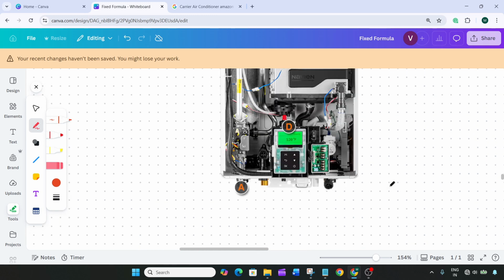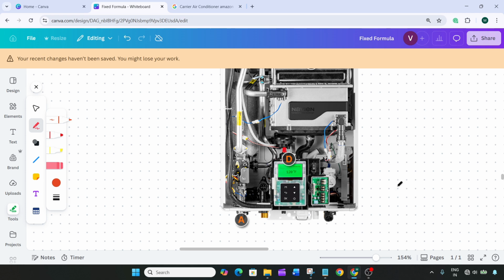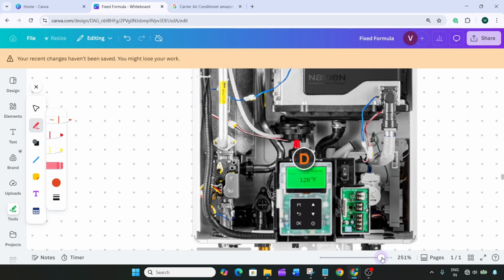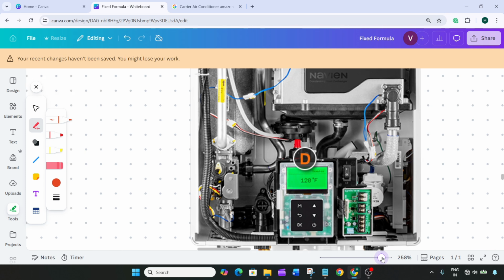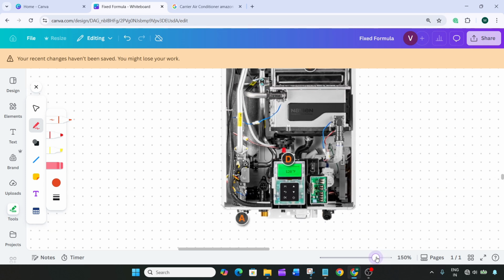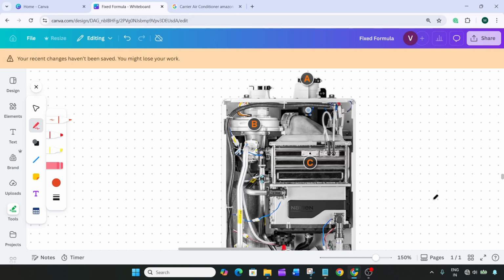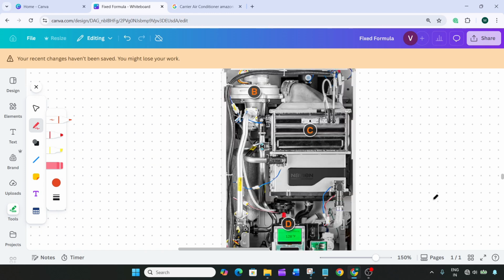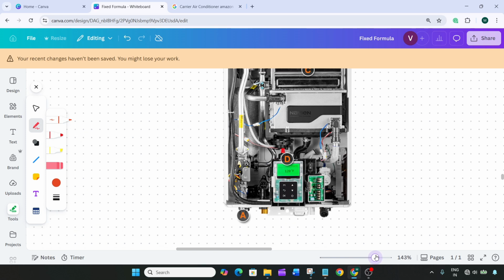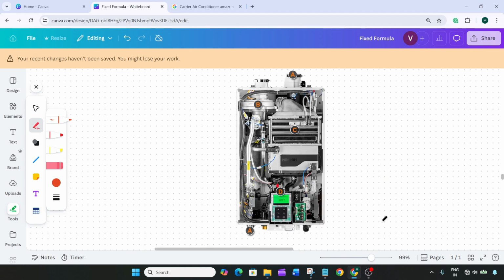After that, look at the control panel for error codes, which tell you exactly what's wrong. Codes like ignition failure, flame detection errors, or heat exchanger warnings point directly to the affected component. Before taking anything apart, perform a simple reset by turning the power off, waiting 30 seconds, and turning it back on. This alone fixes many temporary faults.